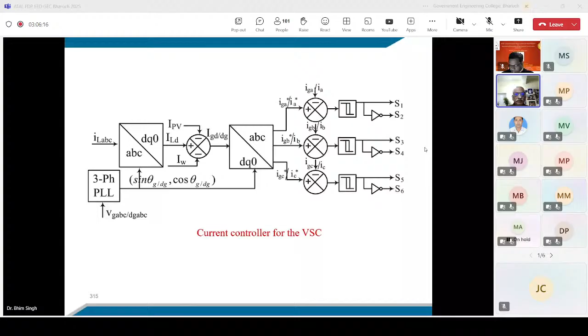When the grid comes, after a few cycles, we are able to synchronize in around 4 to 5 cycles. Our standard allows around 10 cycles. Of course, on desynchronization, you just open it and it works very well in voltage control mode. So we have to change the algorithm from current control mode to voltage control mode.